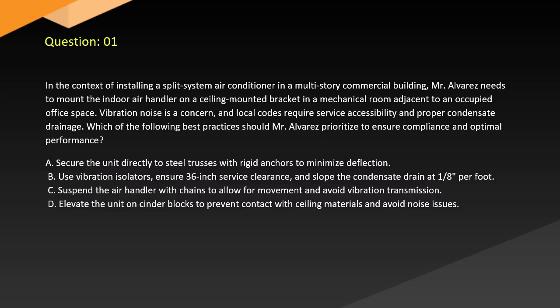A. Secure the unit directly to steel trusses with rigid anchors to minimize deflection. B. Use vibration isolators, ensure 36-inch service clearance, and slope the condensate drain at 1/8 per foot. C. Suspend the air handler with chains to allow for movement and avoid vibration transmission. D. Elevate the unit on cinder blocks to prevent contact with ceiling materials and avoid noise issues.